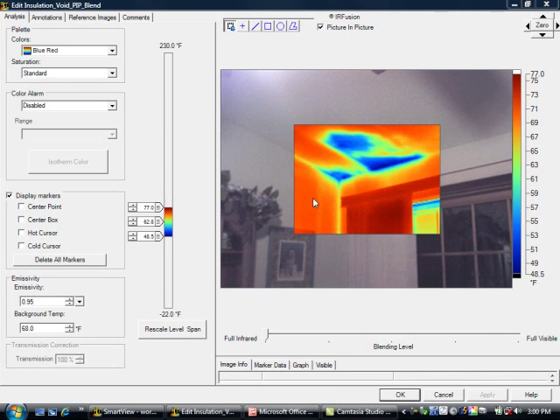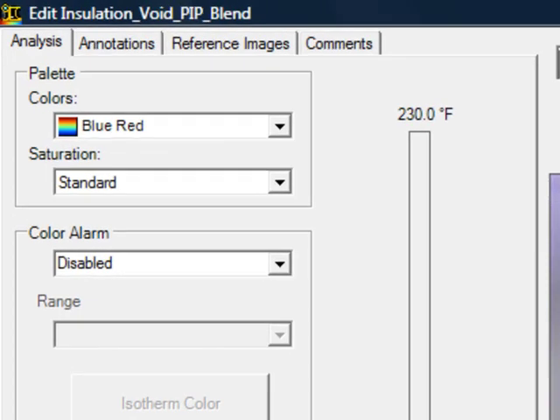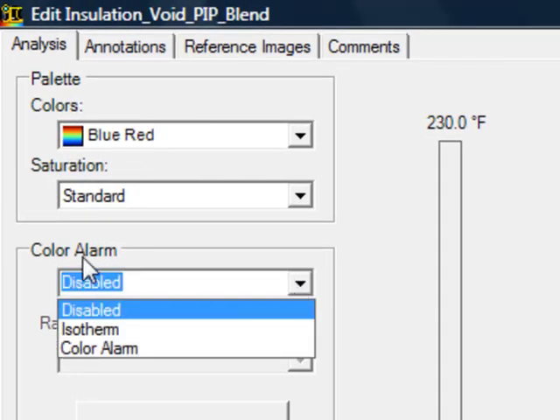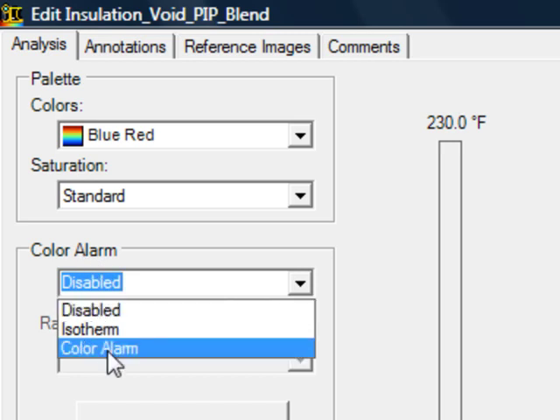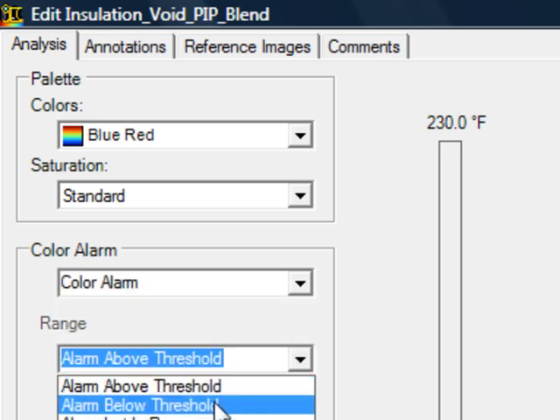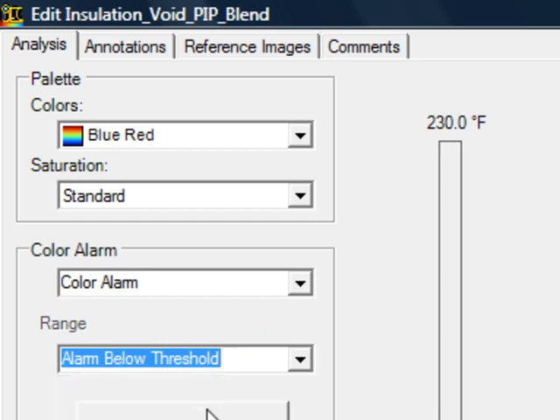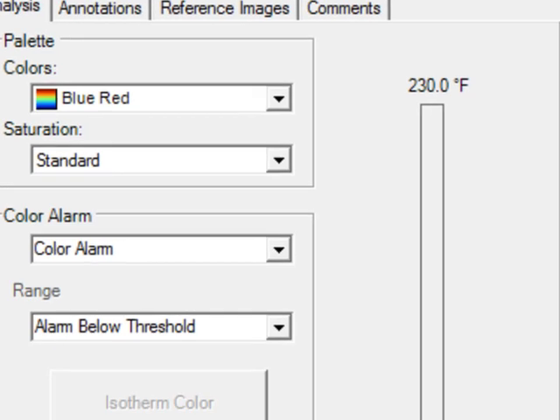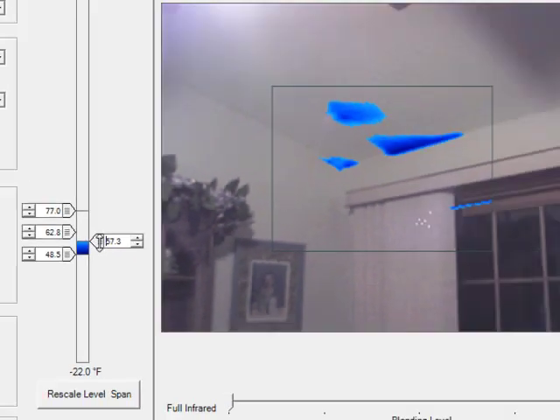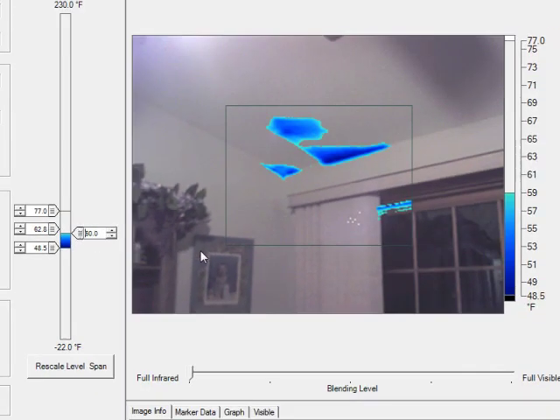So given that, let's say the thermal hygrometer tells me that the dew point is 60 degrees. And let's say my camera is accurate. That being the case, on the software I'm going to take my color alarm and enable it. And I'm going to choose the alarm below threshold. That would mean that wherever I put my threshold, I'm going to put it at the dew point. The dew point we said is 60. So let's go up to 60.